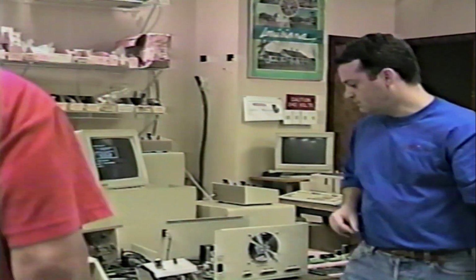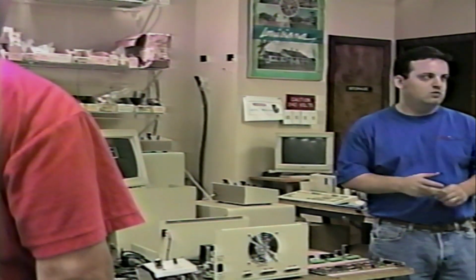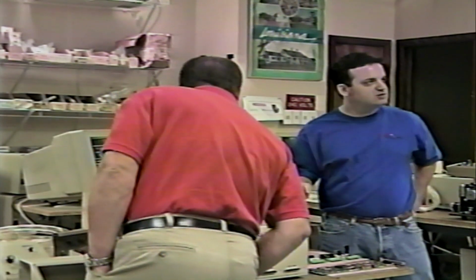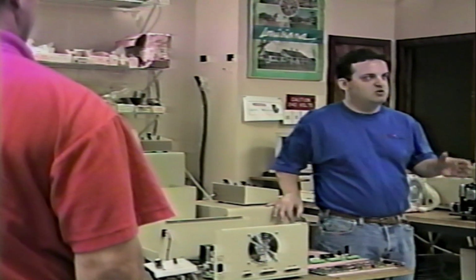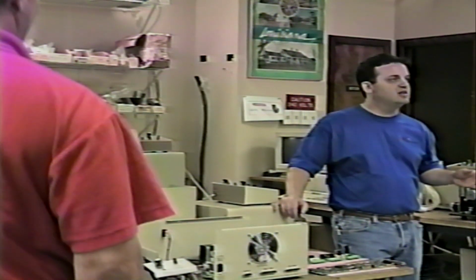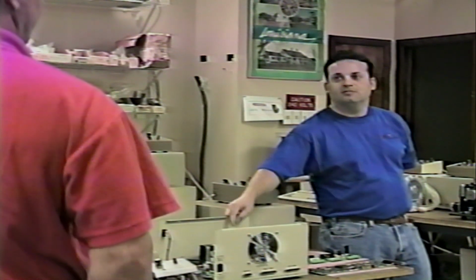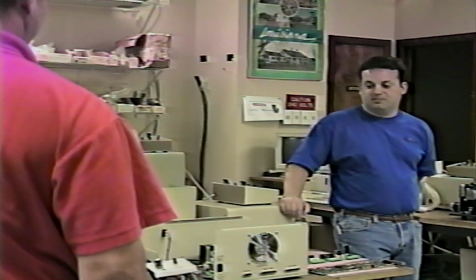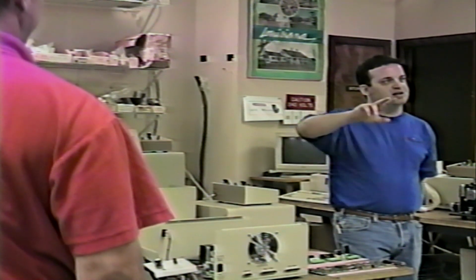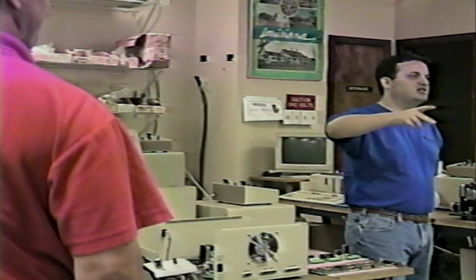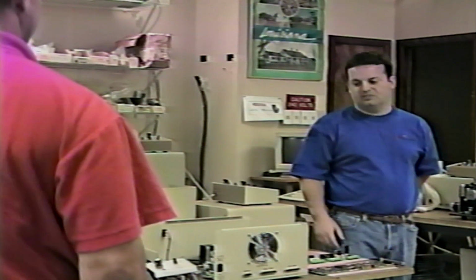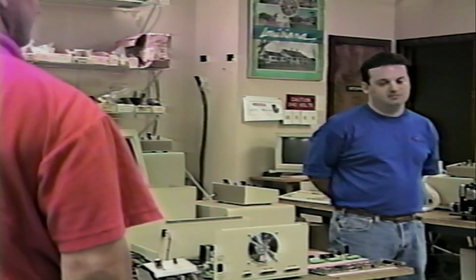No, we had a problem with one of the blocks, and it was causing the machine to do funny things - just a bad ground. We had a customer who had this problem twice. It finally got resolved once we made sure the grounds were torqued down, but you can have unpredictable results. The table can do really strange things with a bad ground - it'll work for a while and then go funny. Basically what was happening is a ground wire would make connection, then lose connection, make connection, lose connection. So it worked fine for a week, then the problem came back again. That was kind of a hard one to diagnose.